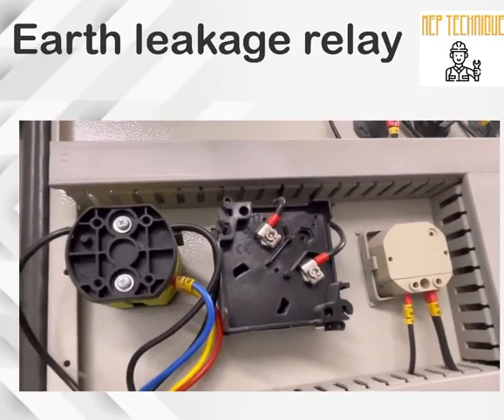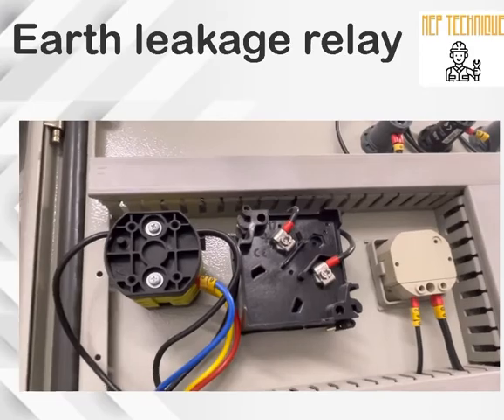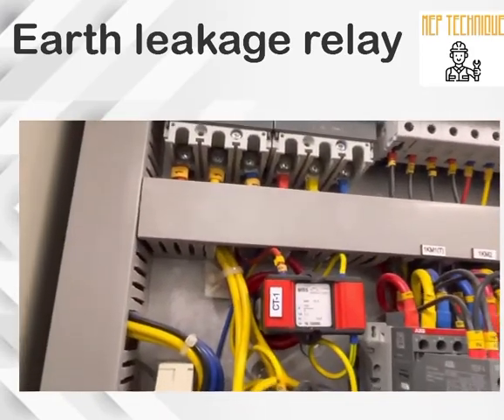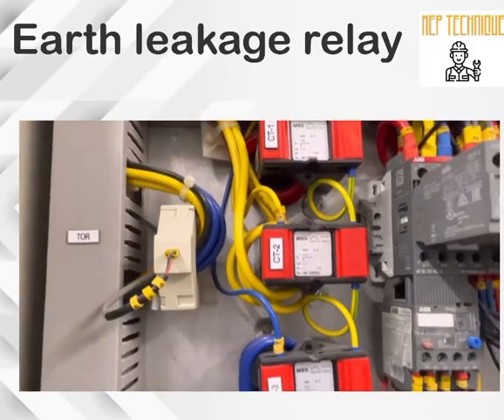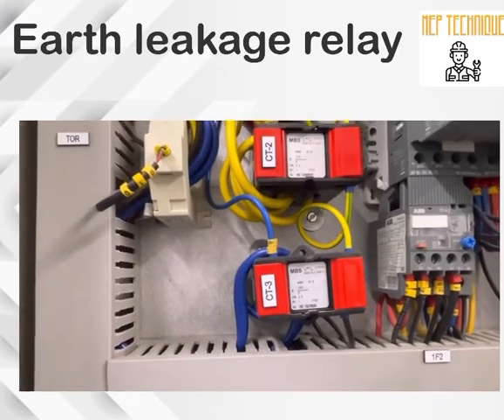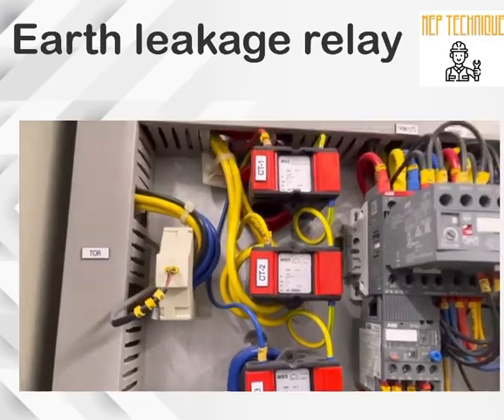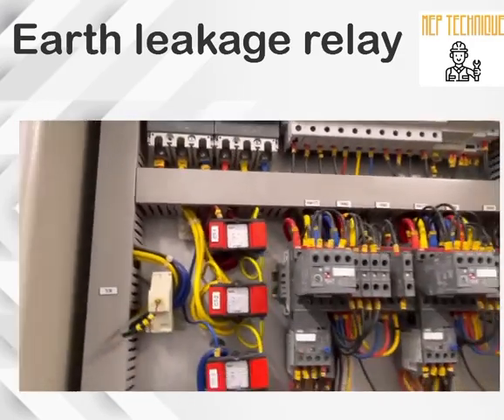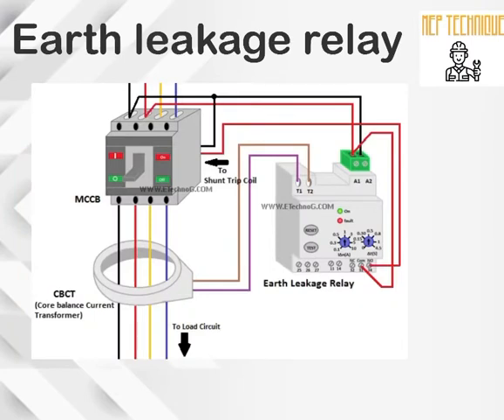We will discuss the ammeter in more detail in our next topic. I hope you understood the earth leakage relay and the core balance current transformer inside the electrical panel. The ELR is connected with the shunt trip coil of the MCCB. In case an earth leakage occurs, the earth leakage relay will trip our MCCB through the shunt trip coil.